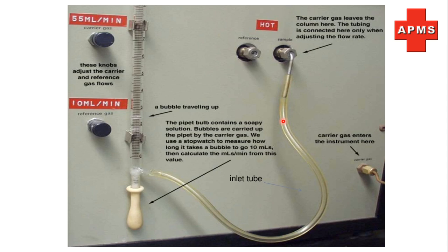But before that, we make the carrier gas flow throughout the instrument in this path to clear the instrument, or to prepare the instrument initially for the experiment. So during that time we attach this type of assembly to this column, and see or control the flow of carrier gas.